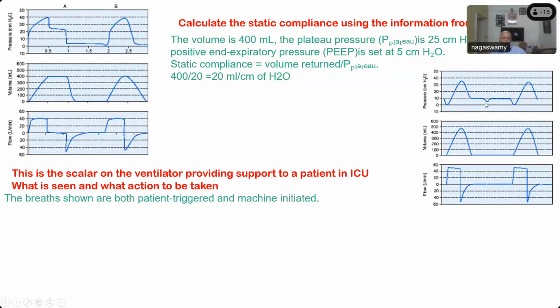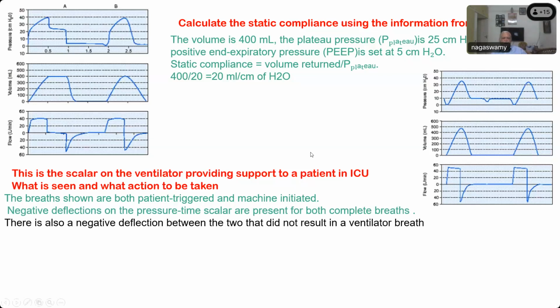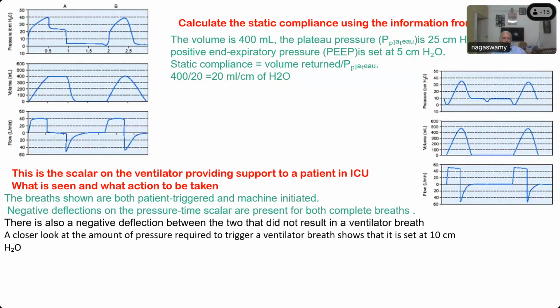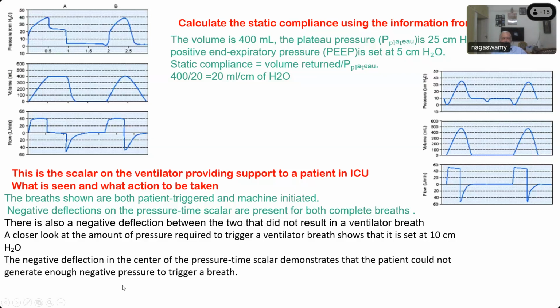The breath shows that both patient triggered and machine initiated breaths are present in this. Okay. Negative deflections on the pressure time scalar are present for both complete breaths. You can see this is the negative deflection from 10 centimeters for both. Whereas there is a negative deflection between the two that did not result in a ventilator breath. A close look shows the pressure that triggered the ventilator is about 10 centimeters. As soon as the pressure has dropped to 10, there is a negative deflection that causes a breath. And the negative deflection in the center of the pressure time scalar demonstrates that the patient could not generate enough negative pressure to trigger a breath.